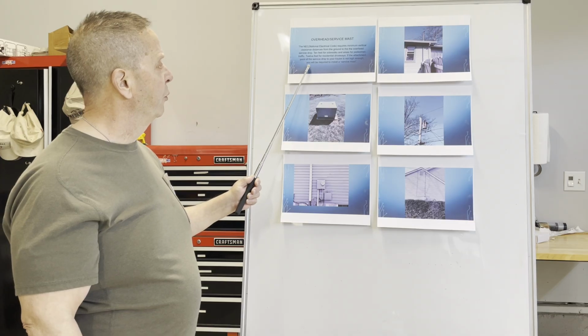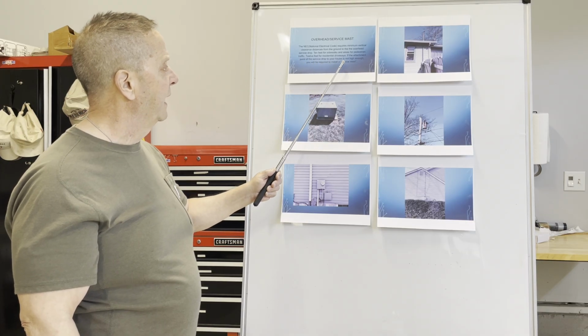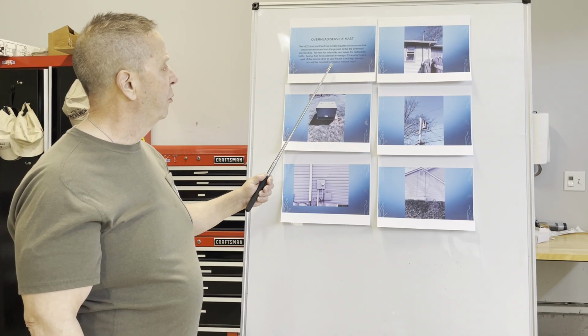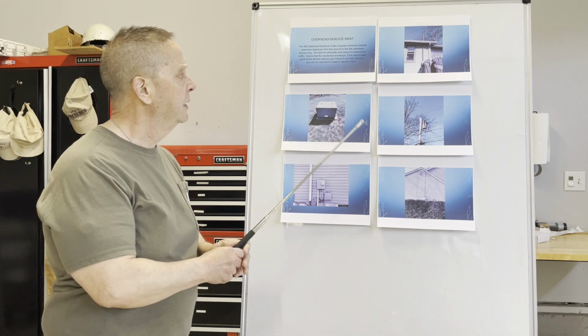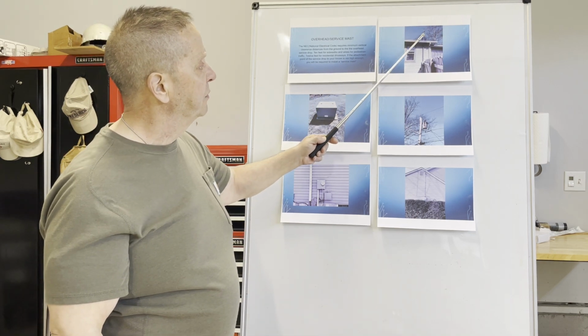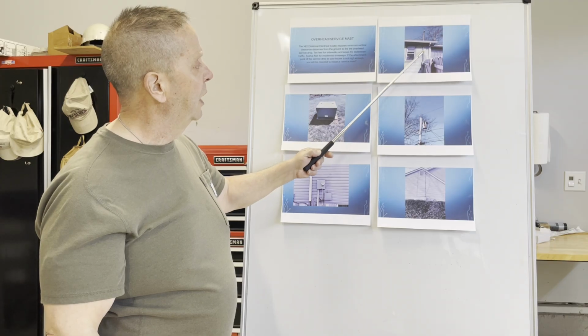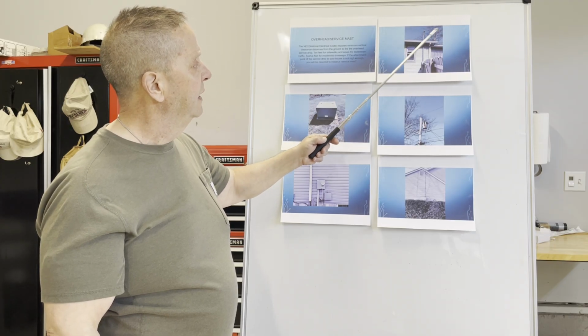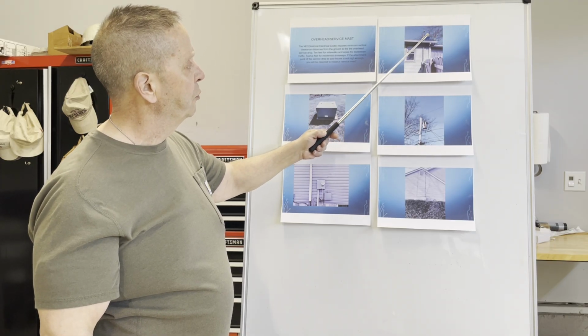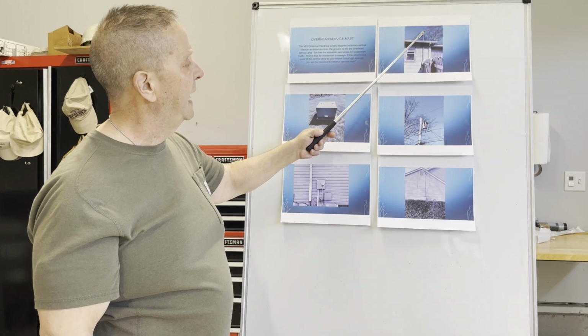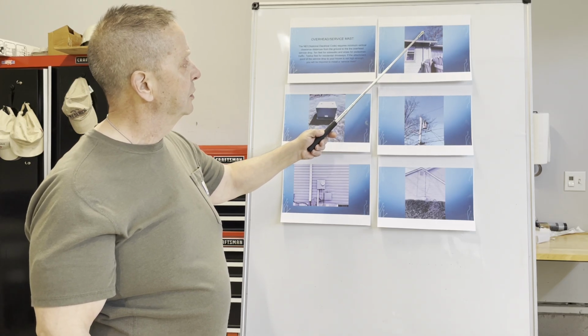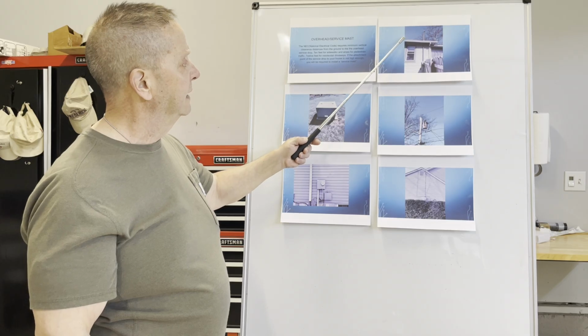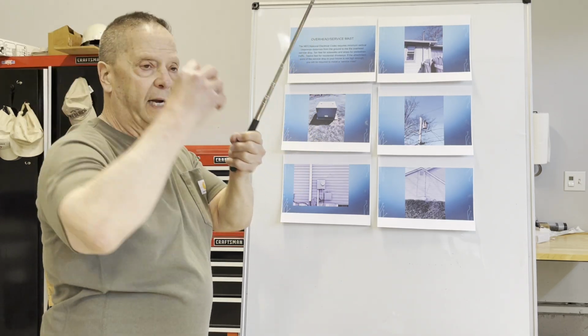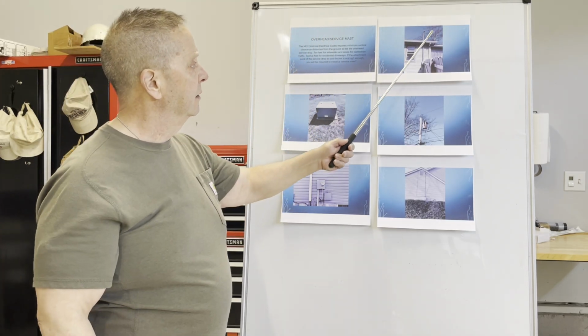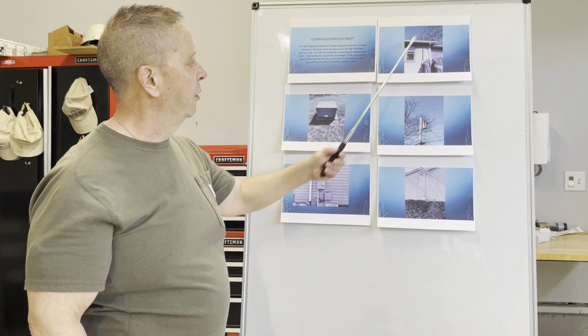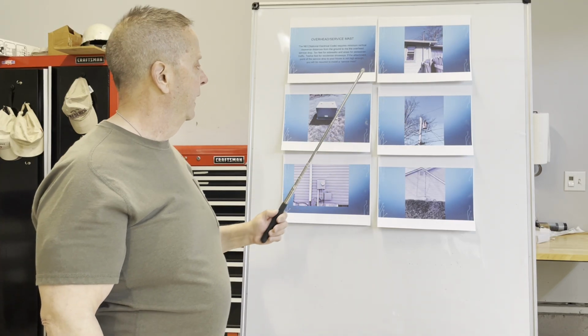If the attachment point of the service drop to your house is not high enough, you will be required to install a service mast. Basically, that is a piece of rigid conduit that goes up through the roof eave. And as you can see, the service drop from the utility comes across and attaches to that. And then there should also be a guy wire that attaches to the roof to counteract the weight of your service drop pulling on that cable.